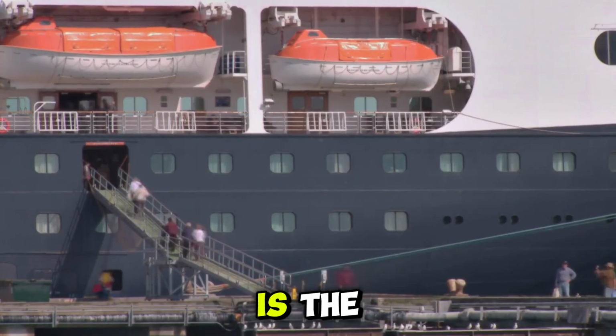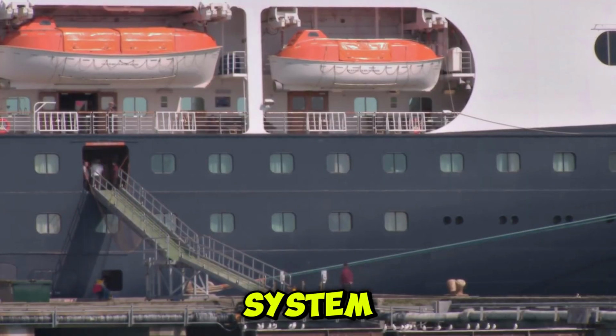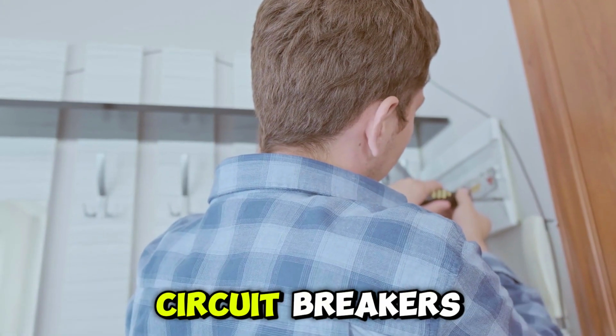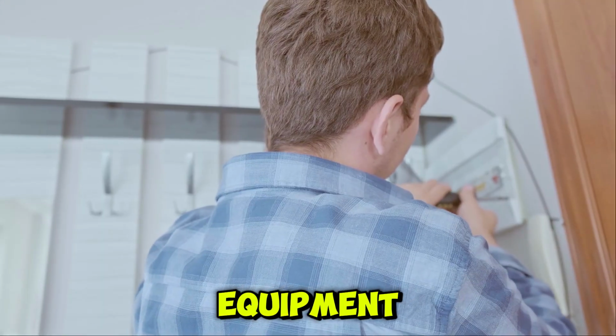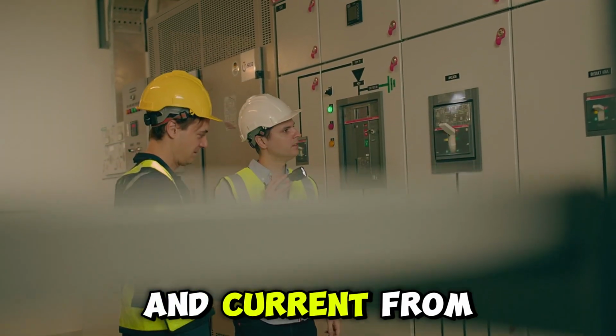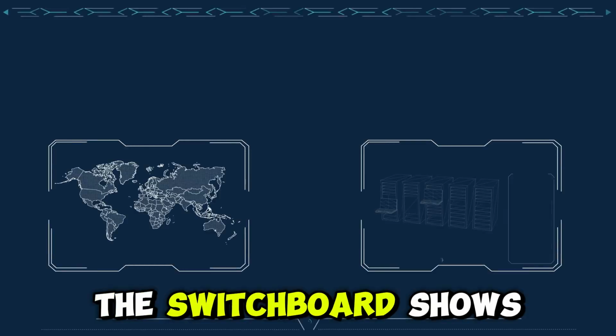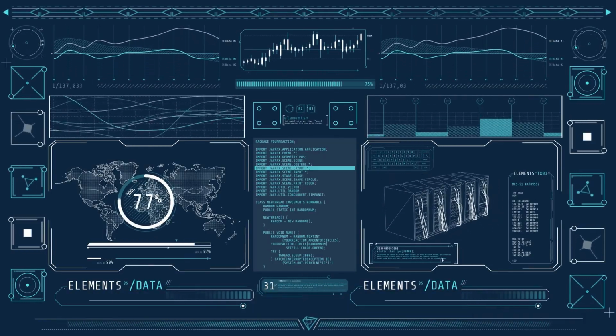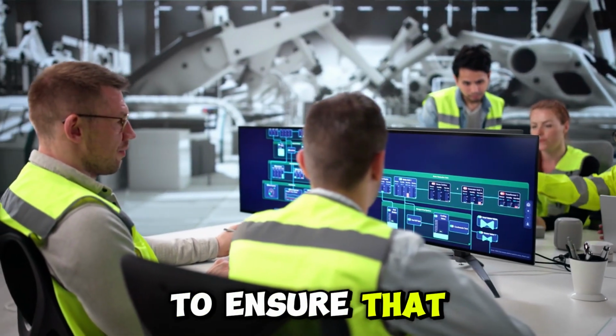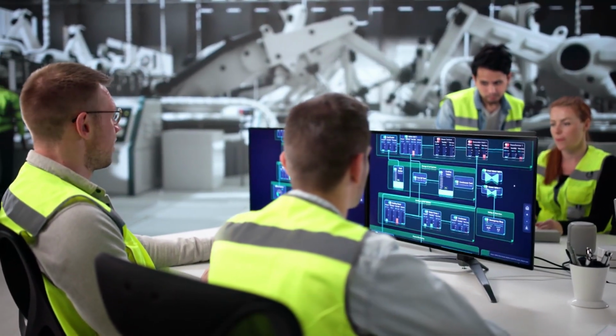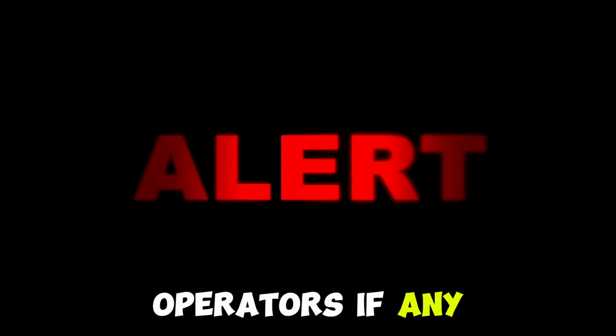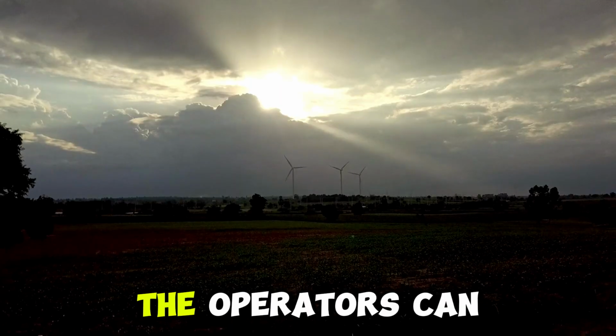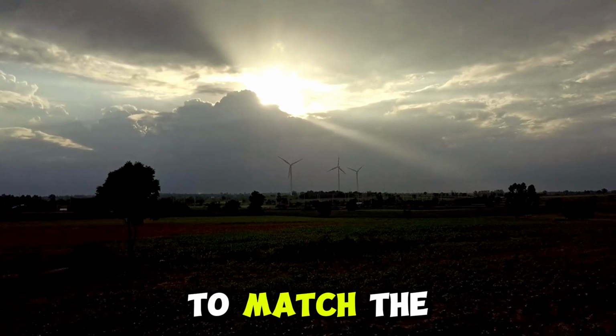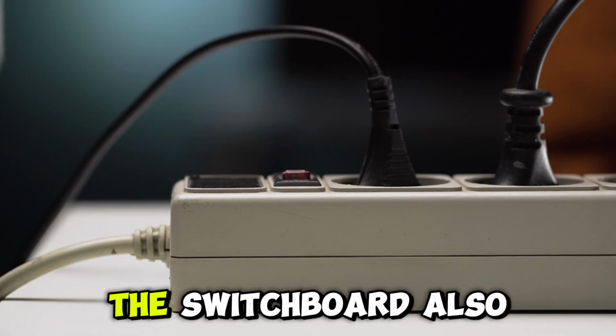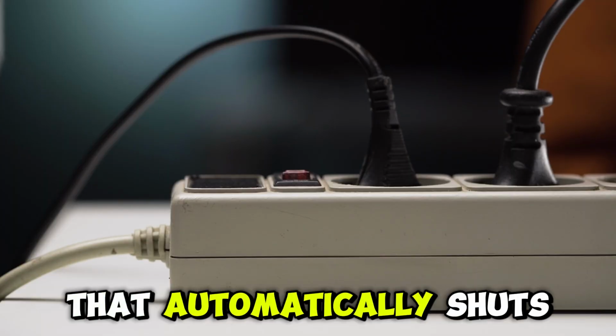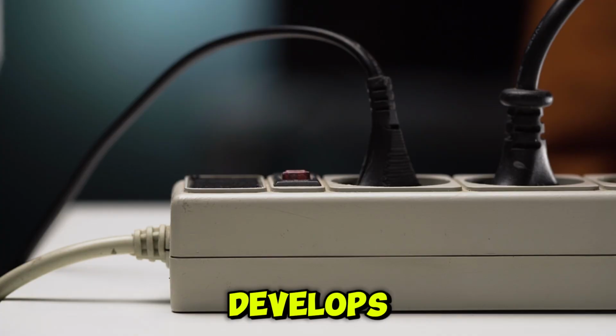The electrical switchboard is the control center for the ship's electrical system. The switchboard contains circuit breakers, switches, and monitoring equipment. The switchboard shows the voltage and current from each generator. The switchboard shows the total electrical load. Operators monitor the switchboard to ensure that the electrical system is operating correctly. Alarms alert the operators if any parameter is abnormal. The operators can start and stop generators as needed to match the electrical load. The switchboard also contains protection equipment that automatically shuts down a generator if a fault develops.